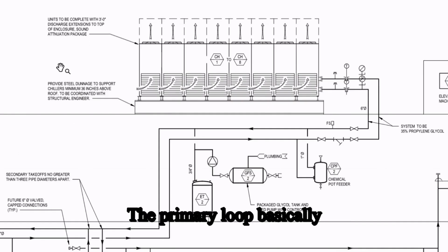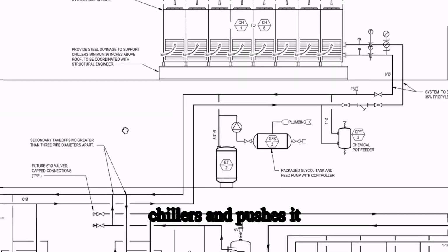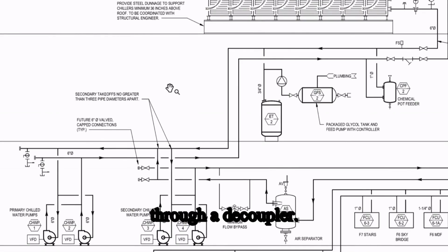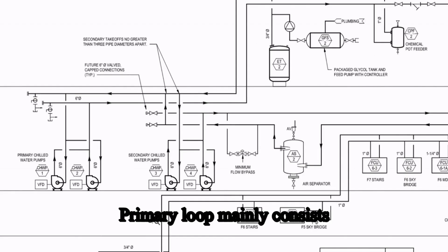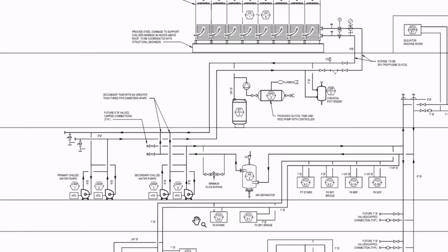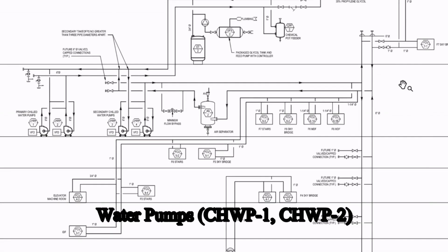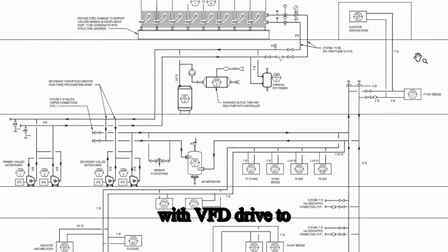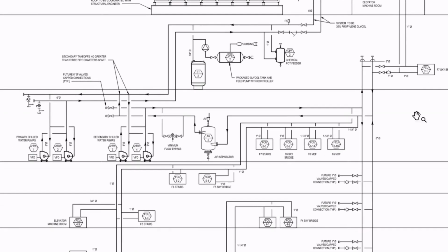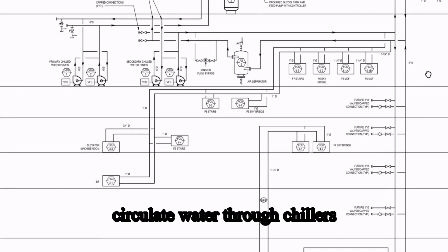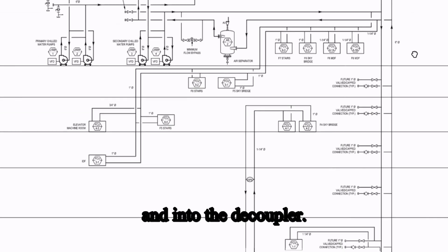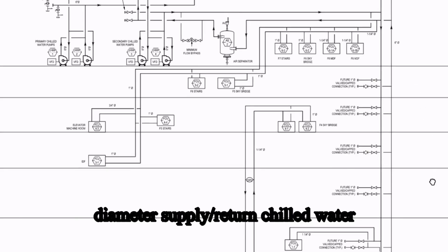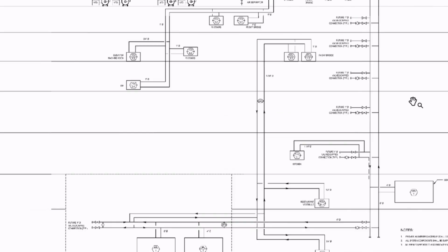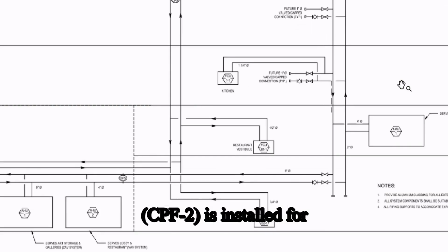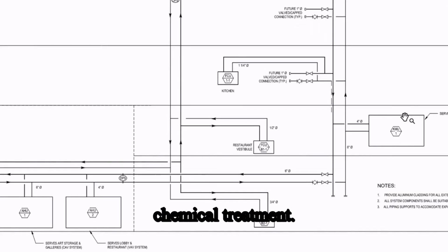The primary loop basically circulates water through the chillers and pushes it into the secondary loop through a decoupler. The primary loop mainly consists of chiller modules, CH1 to CH8, and primary chilled water pumps, CHWP1, CHWP2, with VFD drive to provide stepped flow. Primary chilled water pumps circulate water through chillers and into the decoupler. The piping is 6-inch diameter supply and return chilled water headers. A chemical pot feeder, CPF2, is installed for chemical treatment.